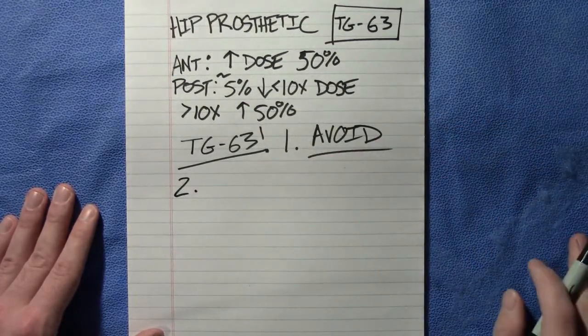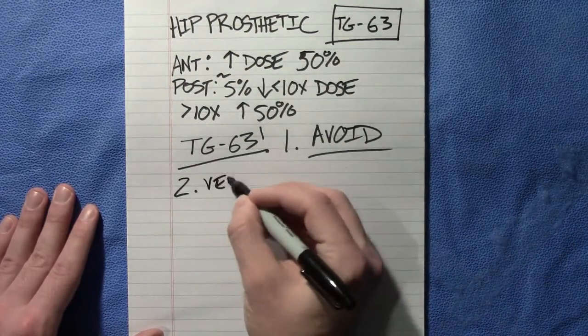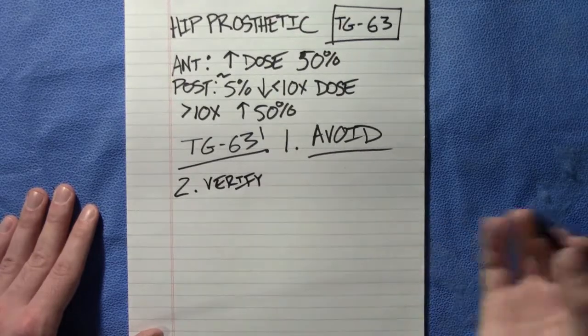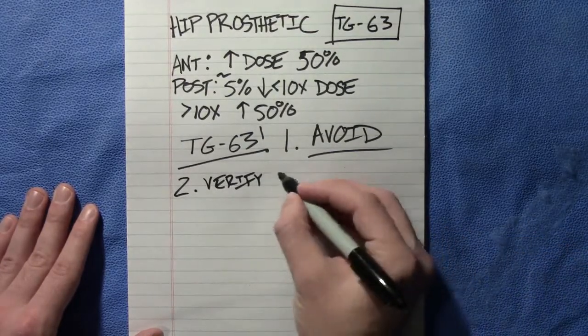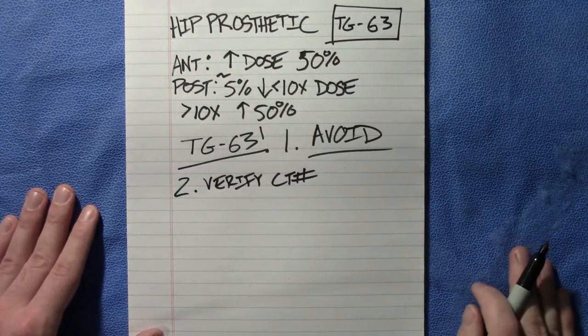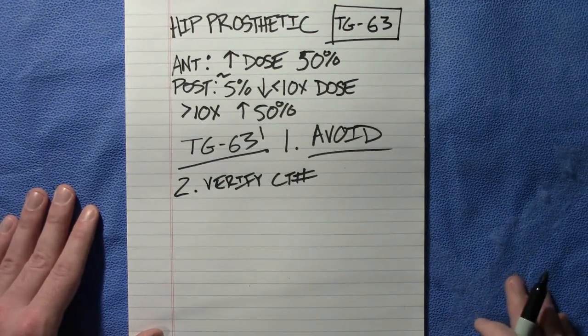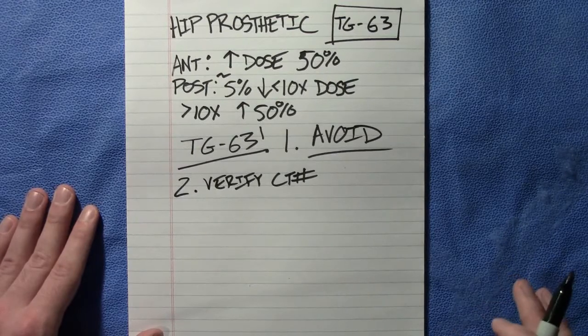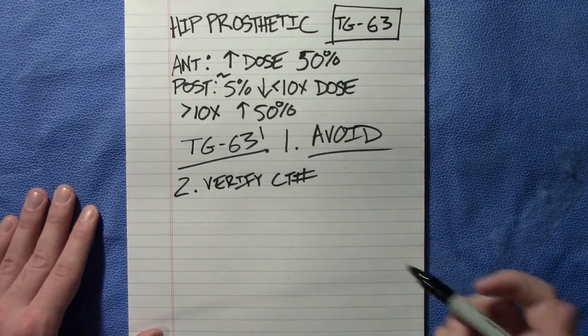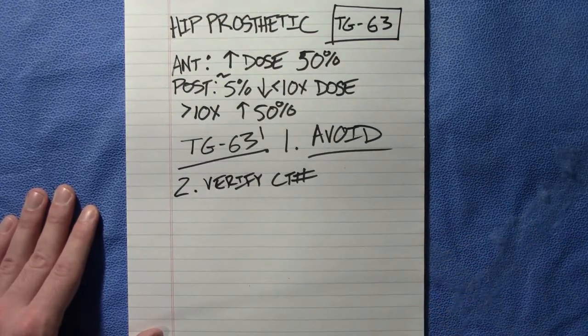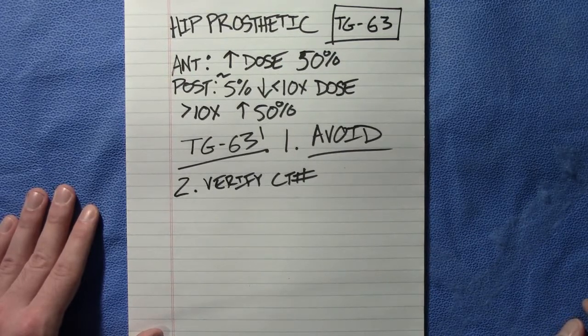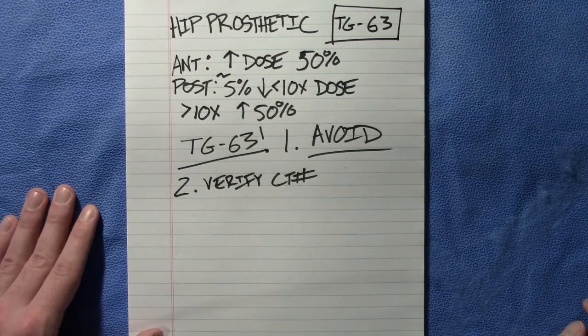Second, verify the CT number — typically by contacting the manufacturer or finding it in a reference resource — because you want to verify the dose calculation. You want to confirm that the CT can image it appropriately, and that your electron density curve goes high enough to capture it. If the CT number (Hounsfield unit) is extremely high, you may not have a corresponding value in your curve, and your dose algorithm will not produce an accurate dose distribution because it won't know how to handle it.